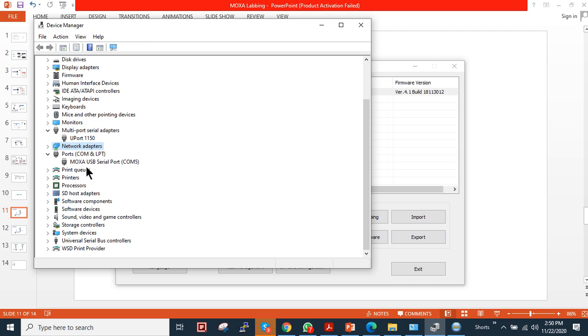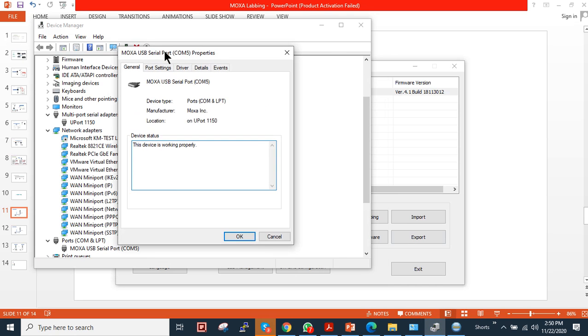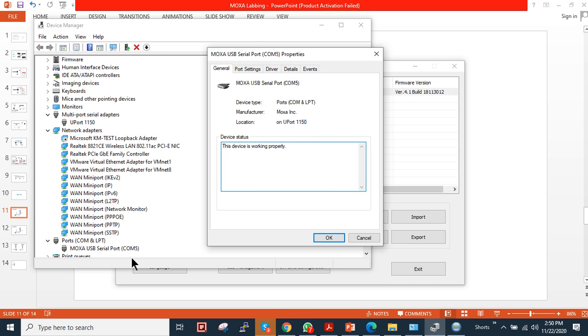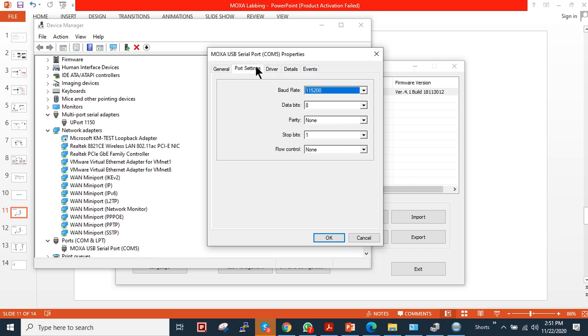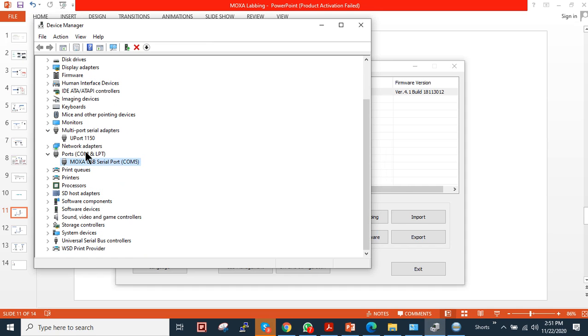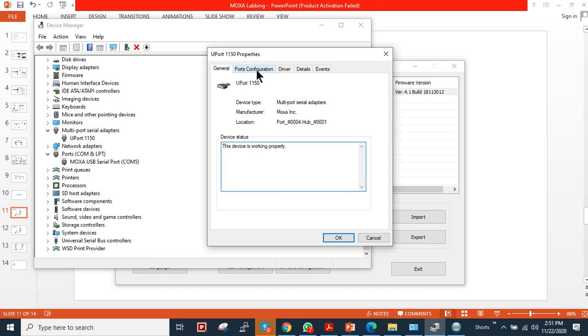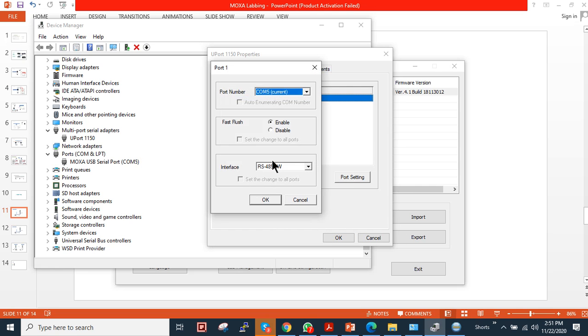The device is discovered. I will show you my USB converter configuration. My USB converter is mapped to COM5, and its baud rate - you can set the baud rate - in my case is 115200 and other parameters are correct. Then you need to verify the serial side. I will click here and see the port configuration. As you can see, it is set to 485 two wire, so it's mapped to COM5 and two wire, which means it is correctly configured.